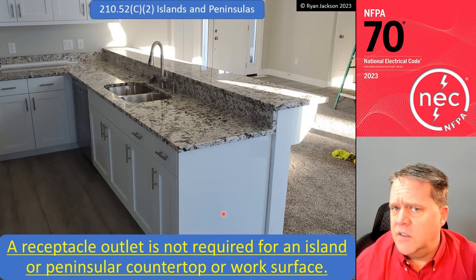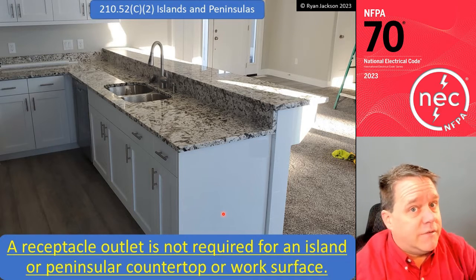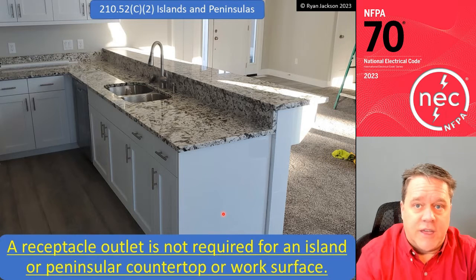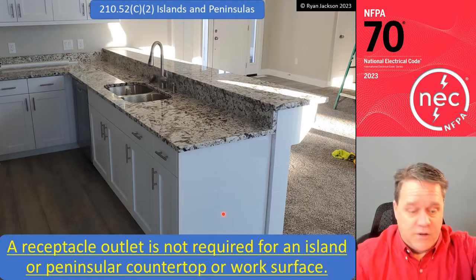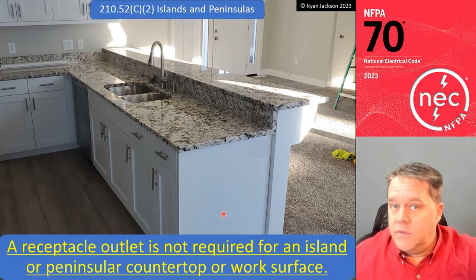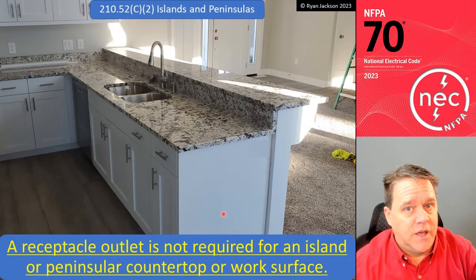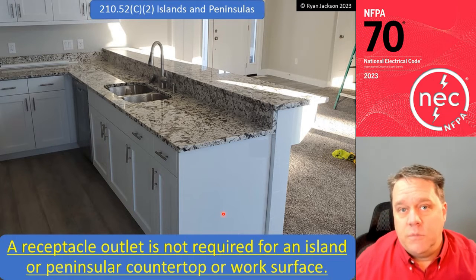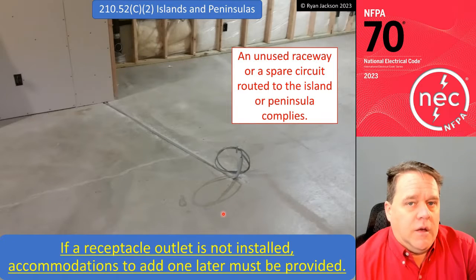314.29, I think, says boxes have to be accessible. Read the definition of accessible. If you put it under the countertop, under the cabinet, and close the cabinet doors and it's under there, that's still considered accessible. I can get to it later if I want without damaging the building finish. So you don't have to have one.